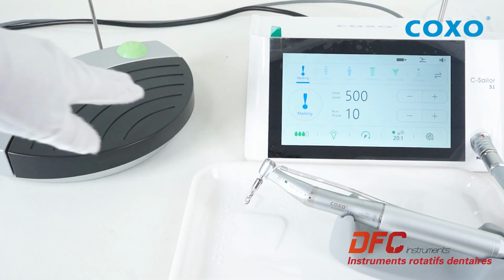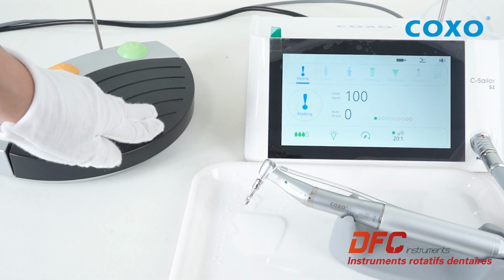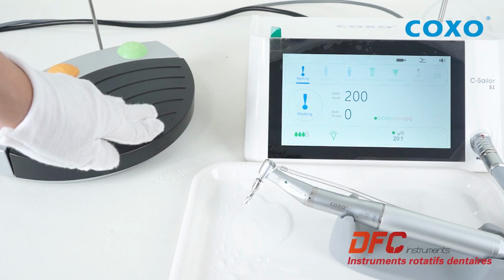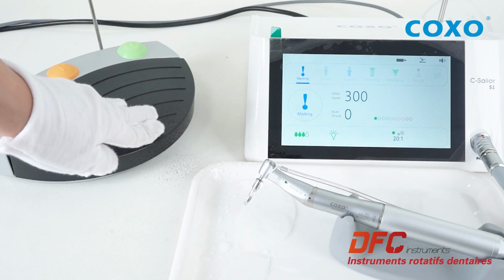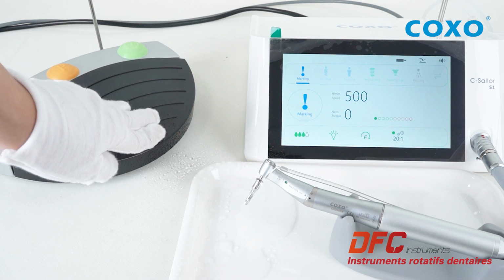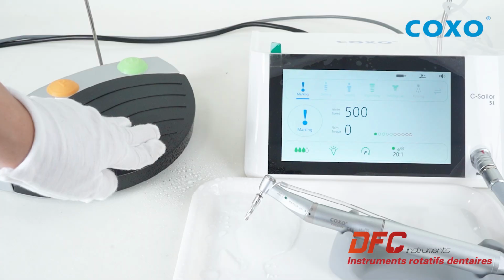To start working, press the pedal. The motor speed depends on the pressure force applied to the pedal. When the pedal is fully depressed, the motor runs at the set speed. When the motor is running, the screen displays the resistance graphically. Green means the limit torque is below 50%. Orange means it is between 50 and 80%. And red means it is above 80%. An acoustic signal sounds as soon as the maximum torque is reached. Release the pedal to stop the motor.